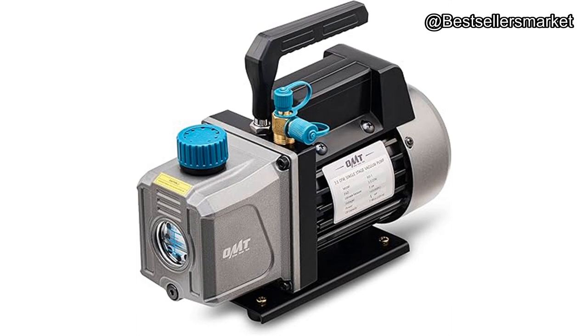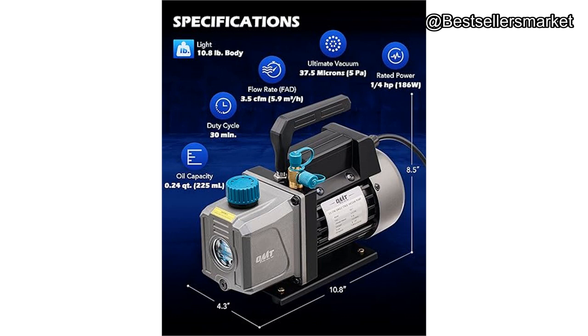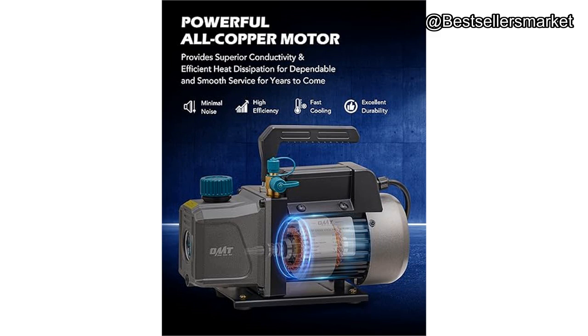Imagine a single-stage vacuum pump powered by a 1/4 horsepower all-copper motor, delivering an impressive 3.5 CFM flow rate. Whether you're dealing with R12, R22, R134a, R410a, or R502 refrigerants, this pump has you covered. It can draw systems down to a precise 37.5 microns, or 5 pascals, ensuring quick and efficient servicing of your AC systems.